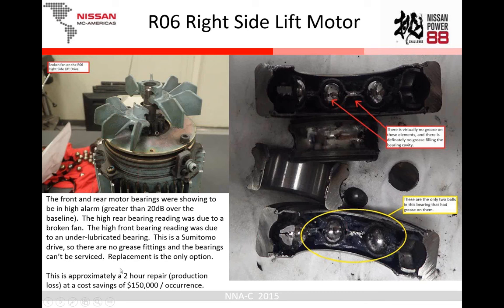This particular one, you can see I had a high alarm on both the motor front and the motor rear. On the motor rear, whenever we took it apart, we found a broken fan. On the motor front, what's interesting is these are sealed bearings. We have lots of drives here at our plant that there's nothing we can do with - all we can do is monitor them and replace them whenever they start to go bad. There are no grease fittings or anything in them. Anything named Sumitomo or SEW Eurodrive, those pretty much none of them have grease fittings - they're all sealed bearings like this.